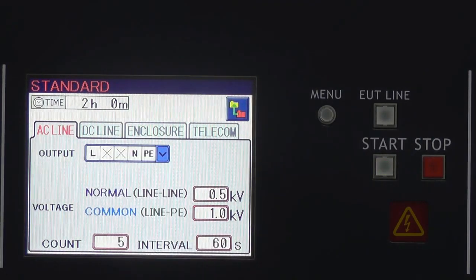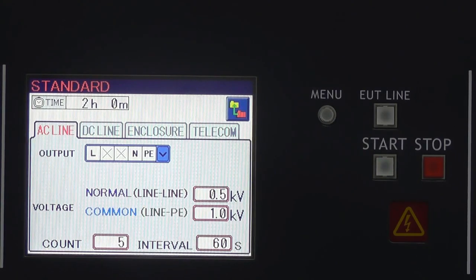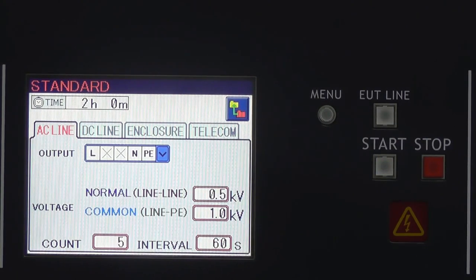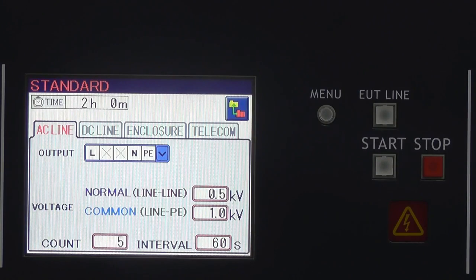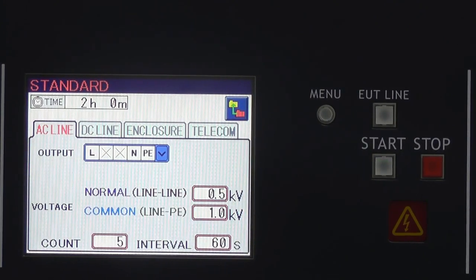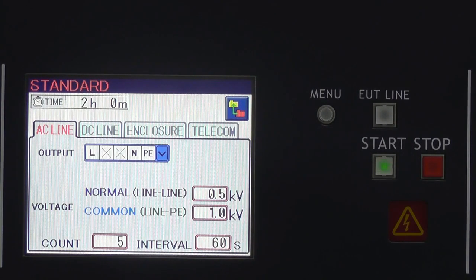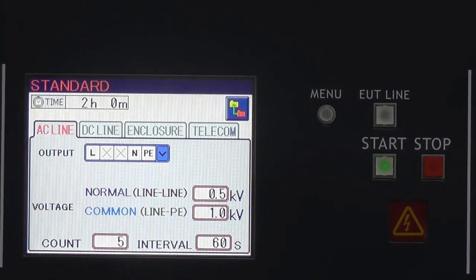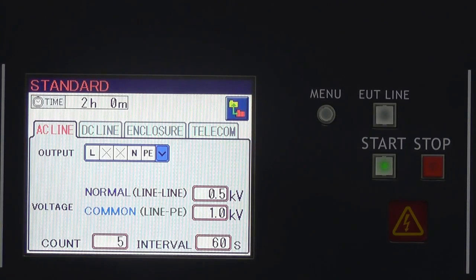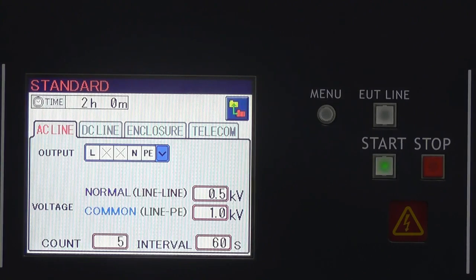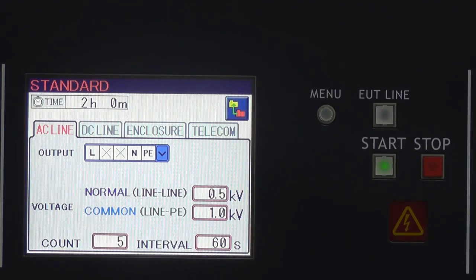And here it shows 2 hours. 2 hours is required for these test conditions. And now you are able to start the testing. All you do is hit the start button right up here. We're not actually going to output the surge today because there's no EUT connected. But if you were going to start, that's how you would do it.